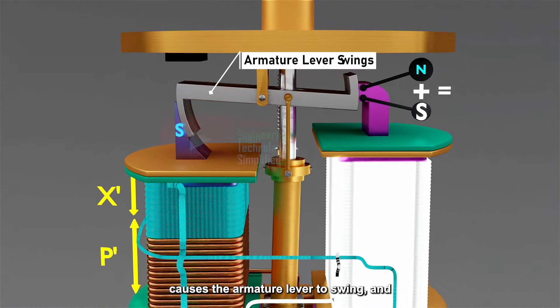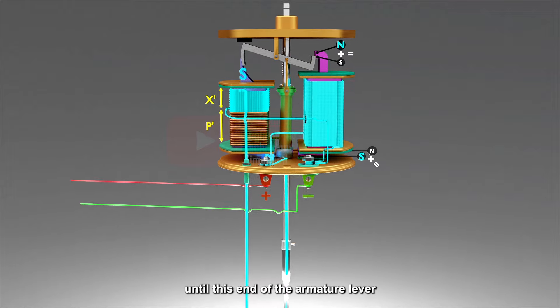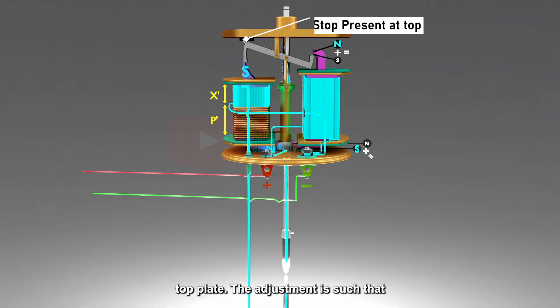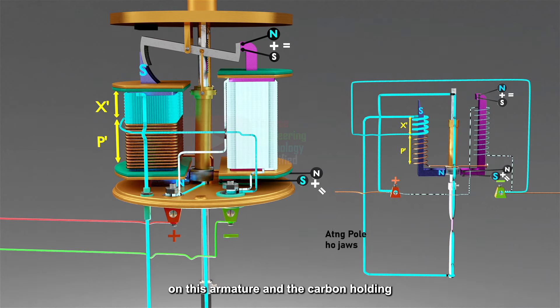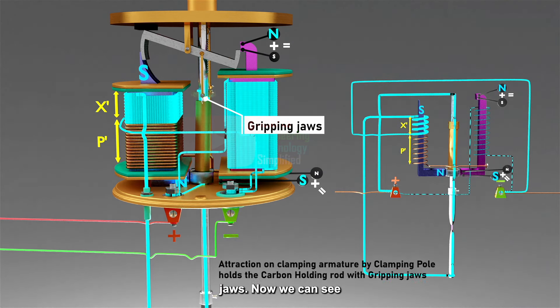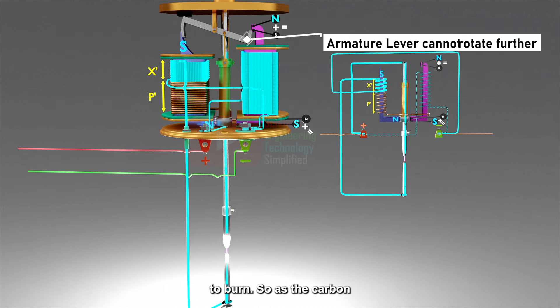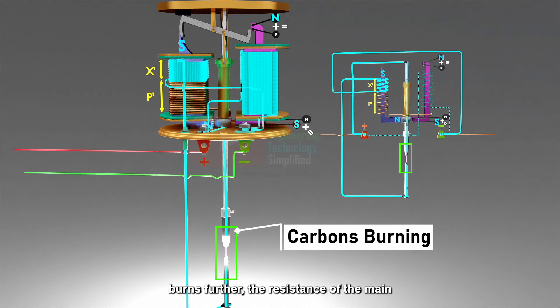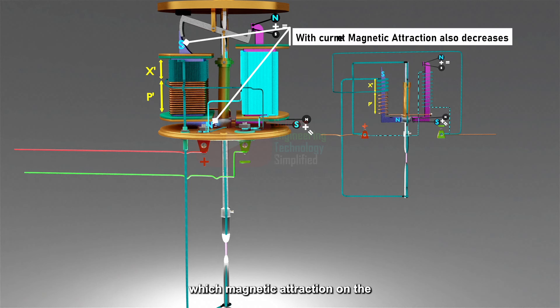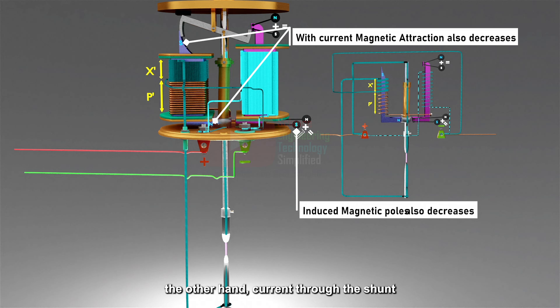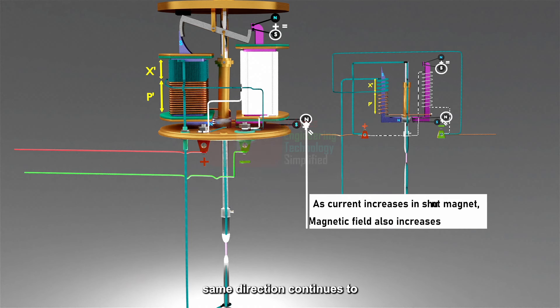This causes the armature lever to swing, and thus this armature descends gradually under the weight of the moving parts, until this end of the armature lever strikes a stop present on the top plate. The adjustment is such that when this takes place, there is sufficient magnetic force of attraction on this armature and the carbon holding rod is gripped securely by the jaws. Now, the armature lever cannot rotate further, but the carbon continues to burn. As the carbon burns further, the resistance of the arc continues to increase and the current through it continues to decrease, causing magnetic attraction on the armature to continue decreasing. On the other hand, current through the shunt magnet continues to increase, due to which the magnetic field in the same direction continues to increase.